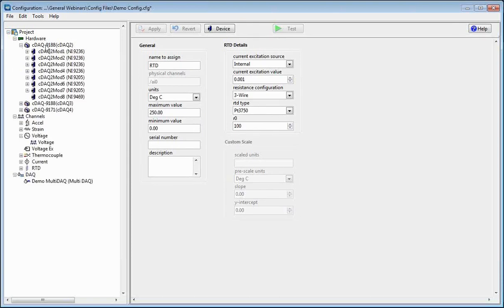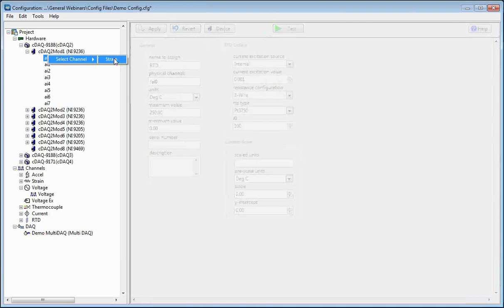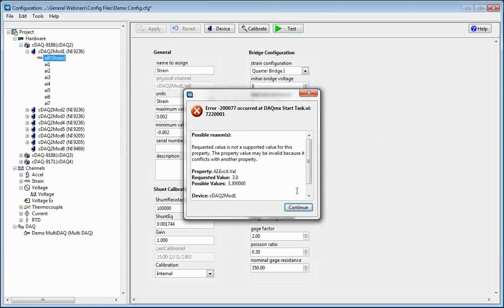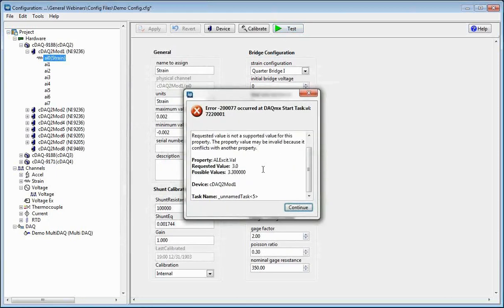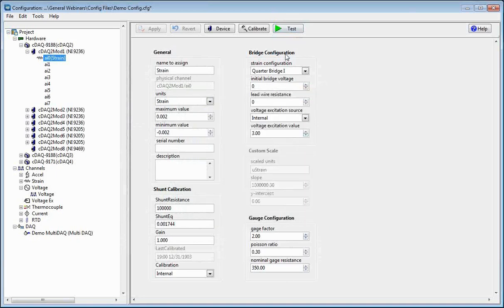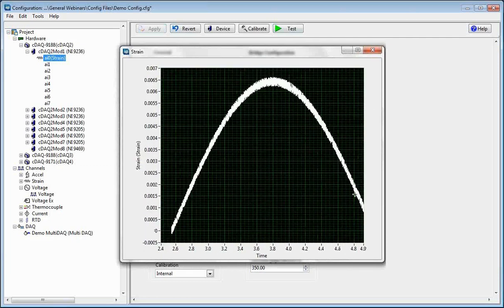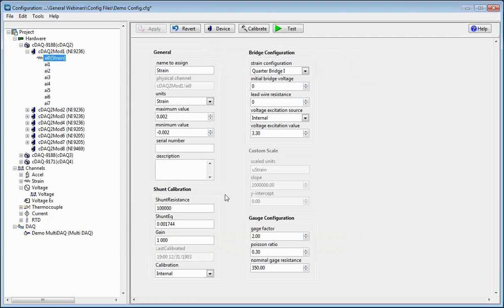The nice thing is, when you go into your hardware — in this case I've got a 9188 with a 9236 module, and we know those modules are only for strain — if I right-click and do Select Channel, all it's going to give me are my options for strain channels. So I apply that strain channel. If I test it, I've got simulated data. Note that it gave an error because my excitation value wasn't correct — it required 3.3. Once I apply that change and test again, we have simulated data. That's a nice way to verify that all your values are filled out correctly before running your test.